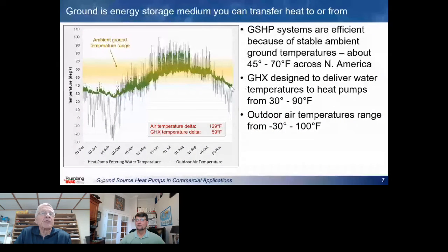And as I said earlier, one of the biggest benefits is that we're working with much more moderate temperatures. If you look at the dark green line here, that's the typical temperature range that you would see in a ground source heat pump in a residential or small commercial application, anywhere from about just around freezing point up to about maybe 70 or 80 degrees, whereas the air temperature might get up to 100, 110 degrees or down to -30 or -40. We've got a much more moderate temperature, and that's where the efficiency of the heat pump comes from.